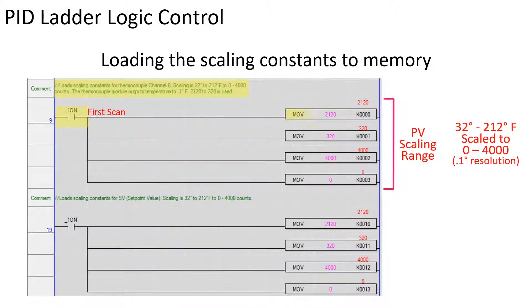On the first scan, 2120 is moved to memory location K0. This represents 212 degrees with one decimal place. A value of 4000 is moved to location K2. A value of 320 is moved to location K1. A zero is moved to location K3.